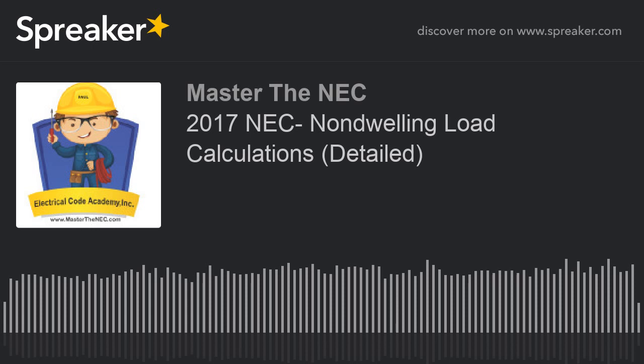So that's what my show window lighting VA is going to be. And that's just step number 9. You're just following down the list. Boom, boom, boom, boom, boom. And I would write that down. Again, if you have no show window lighting, you're not going to add it. Okay? You're going to have sign and outline lighting on a commercial space because there is going to be an entrance to the public. Okay? But you might not have track lighting. You might not have show window lighting. So, again, you're only going to apply these steps if they're applicable to whatever your calculation is.